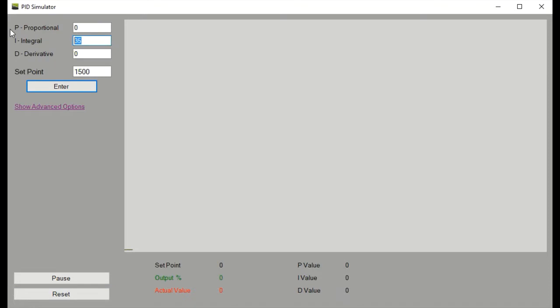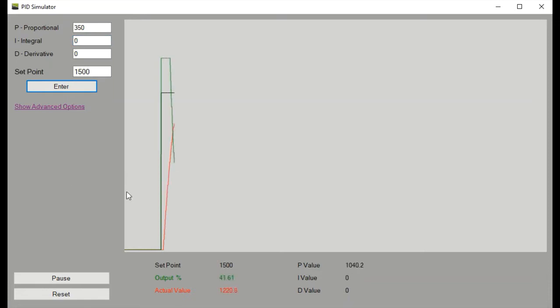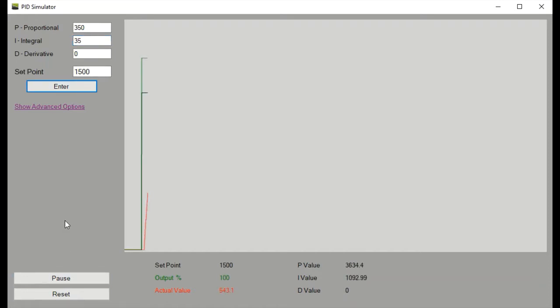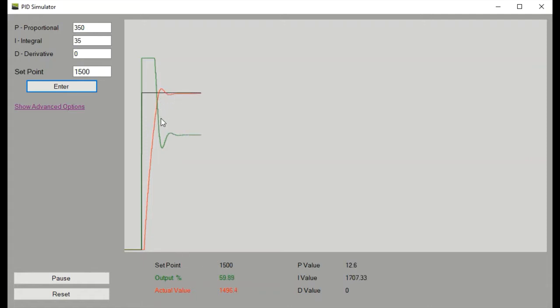Remember when we had just set the proportional to 350 and we had a great immediate reaction, but the actual value never reached the set point? Let's see what that does with our new integral value of 35. We have the immediate reaction from the proportional and then the accumulation over time from the integral to bring that actual value up to the set point.